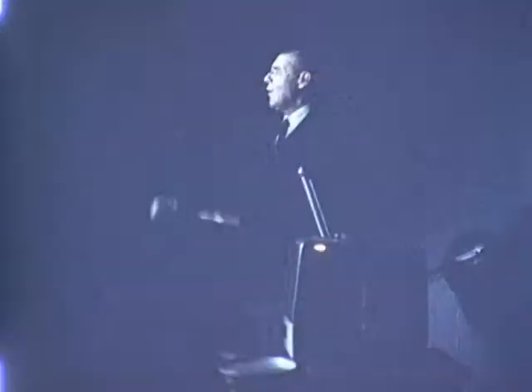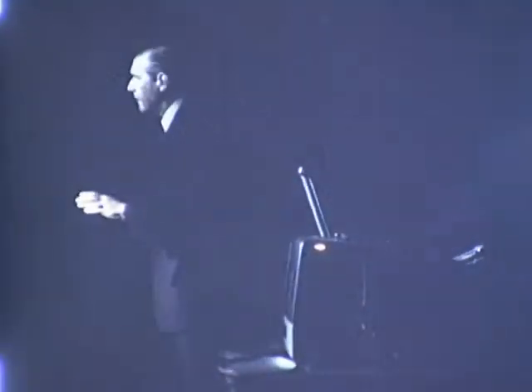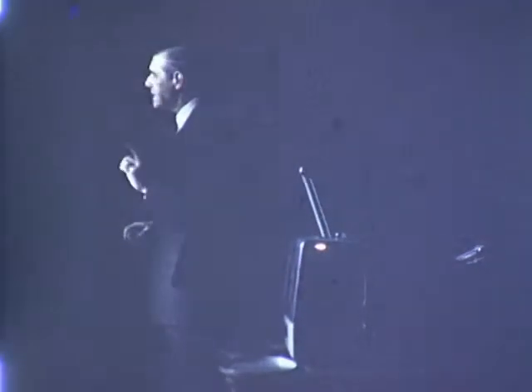Well, that is the IC story. The moral is, beware of inadequate interrupting capacity. Now wait a minute. Just one more thing. This film clip shows an actual test of an old oil circuit breaker. It's going to attempt to interrupt twice as much current as it was originally designed to handle. Watch now. Short circuit is about to be applied.